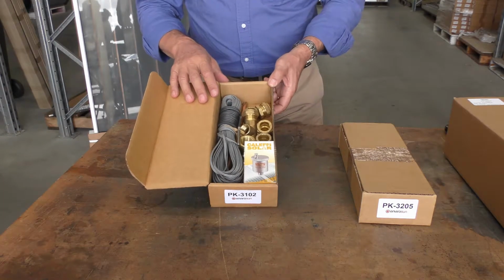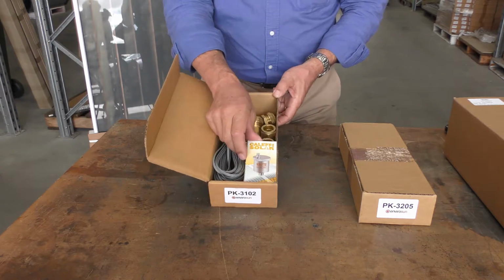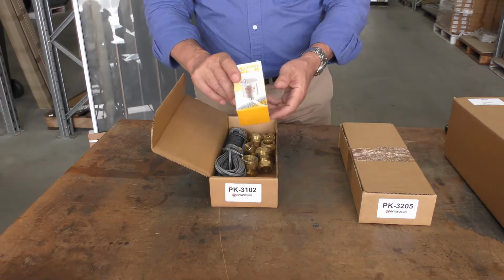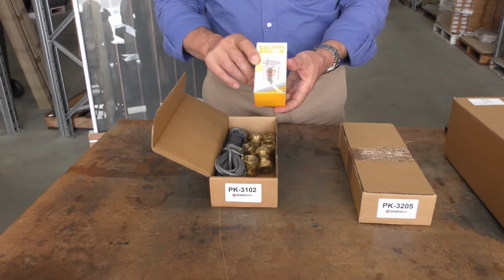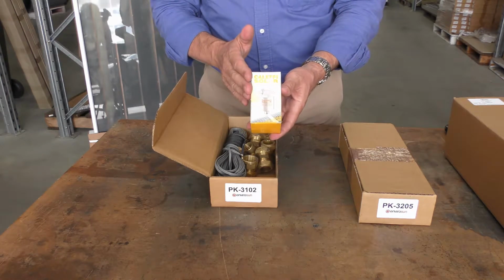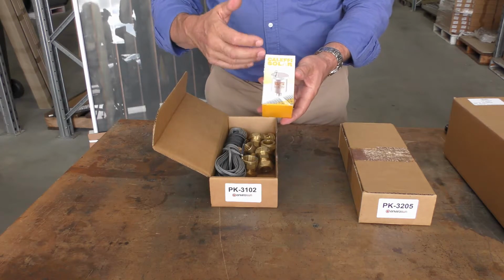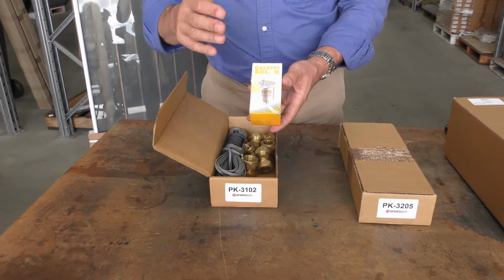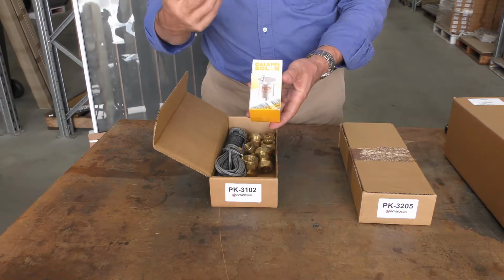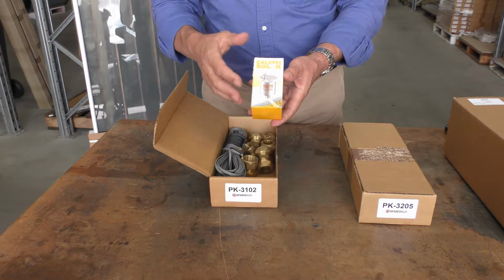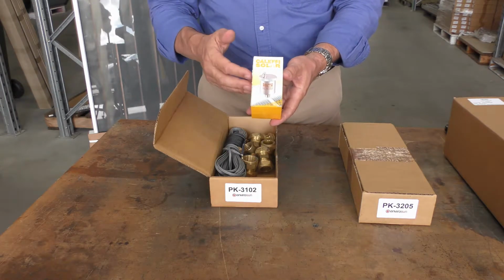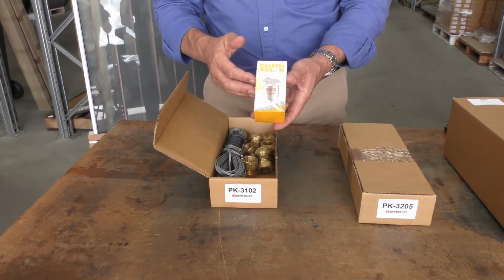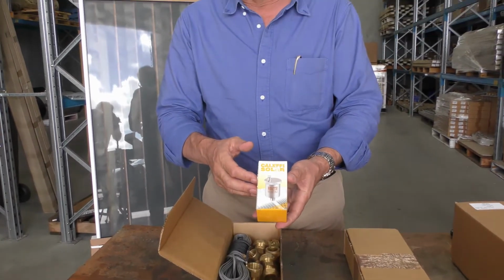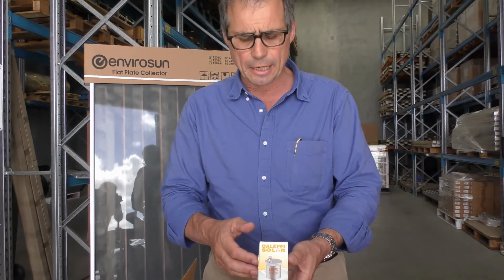Part numbers are PK3102. What do we have in here? Okay, so first is a solar air vent valve. This is fairly important. A lot of companies don't provide this. What is the purpose of this? Well, water has a lot of gas in it. Air gets in the system, particularly just after commissioning. And because the collectors are on the roof, gases and any of the air and so on in the water system will always percolate to the very top of the collector, and in doing so, because we've got a pump there, it can cause problems with the pump not being able to circulate. And when this happens, your pump's just free spinning and not actually doing anything to circulate the energy from the collector back into the tank.